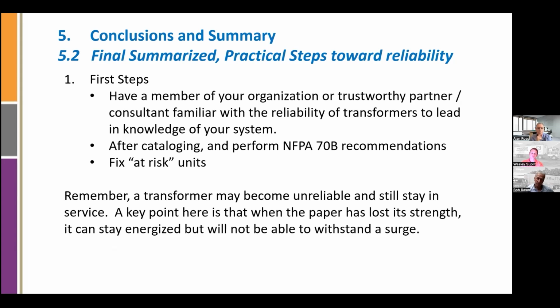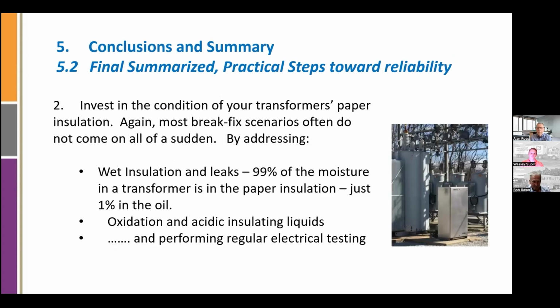And then, fix the at-risk units. Repeating again, a transformer can stay in service, and you may say, well, it hasn't done anything bad yet, but it's weakened. And in the event of a surge, that's when the failures happen. Wet insulation can be dried, keeping after oxidation, performing regular electrical testing. Looking at the LTCs in the transformer is another thing to do. I'll slide on that in a minute.